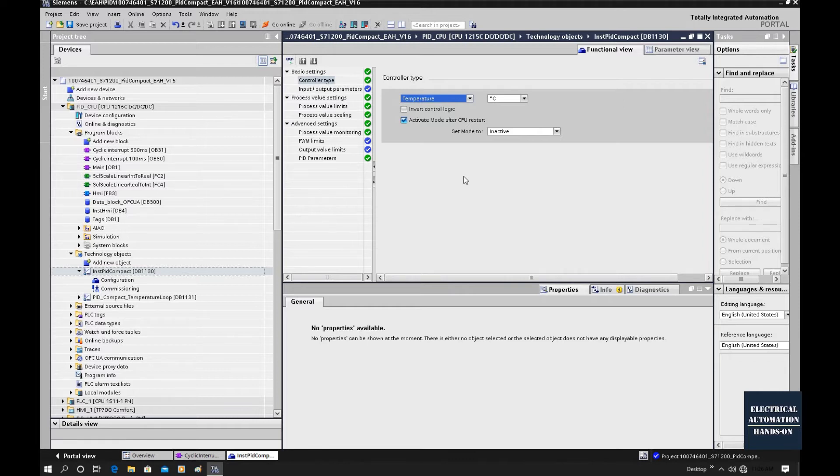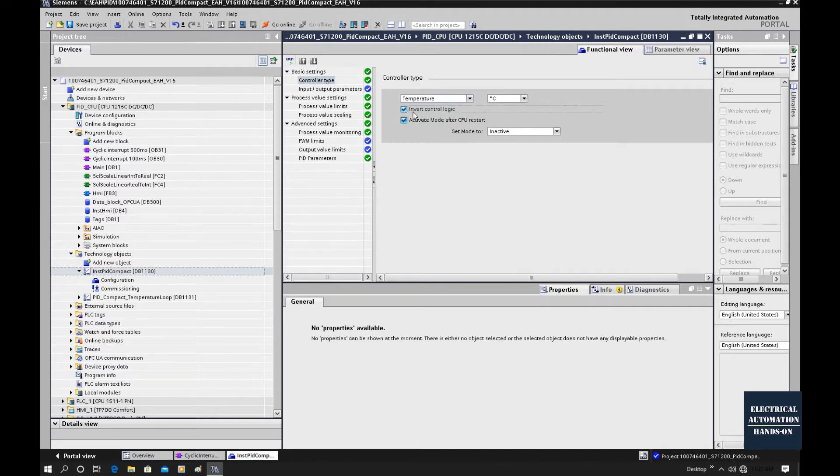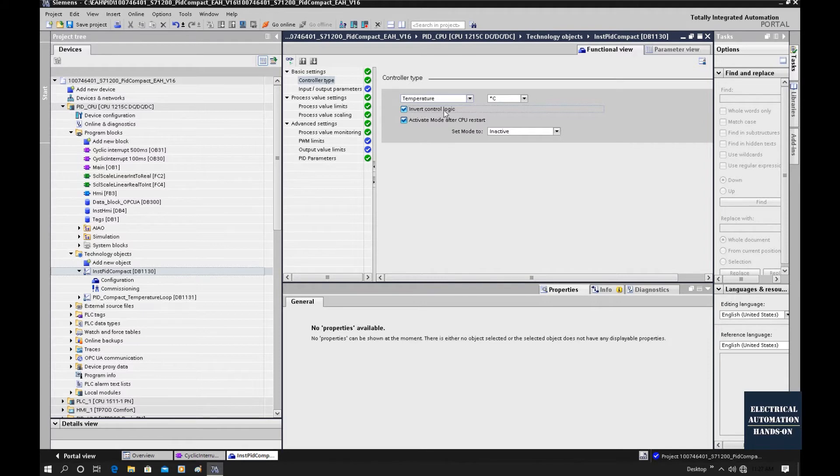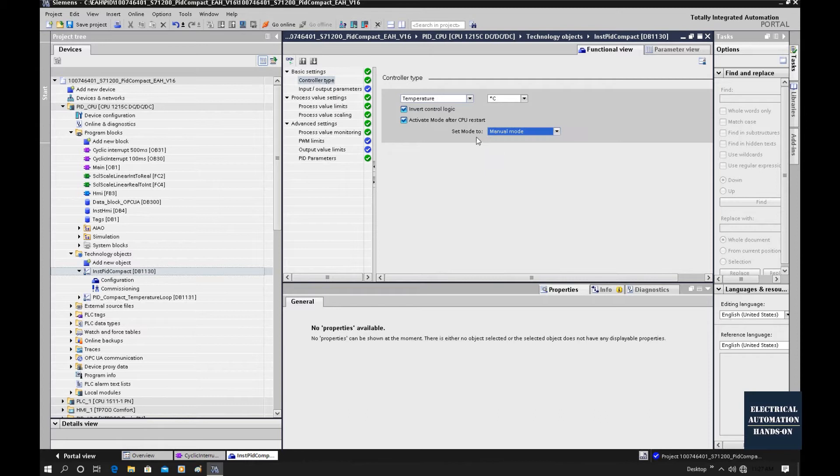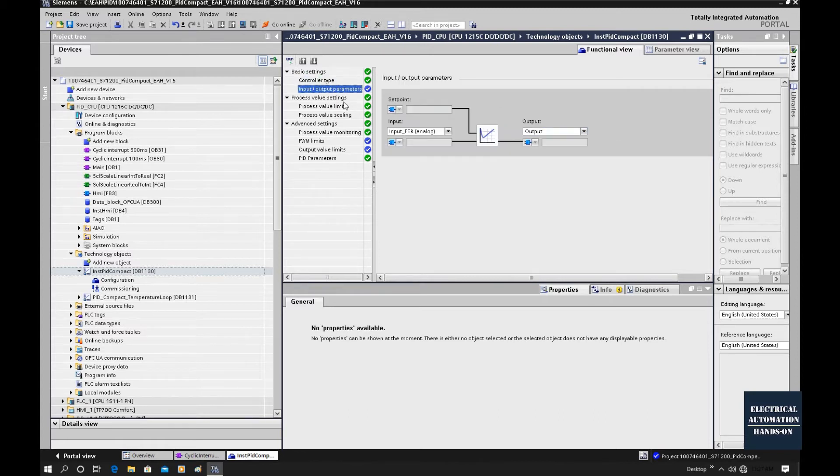That's because in this system, it's a cooling system. That means if the PID output goes higher, the process value, that is the temperature, will go down. The logic is inverted. So basically our K, the gain parameter, needs to be a minus value. If we check this, that means our gain is minus. Active mode after the CPU restart, I will select the manual mode as default.